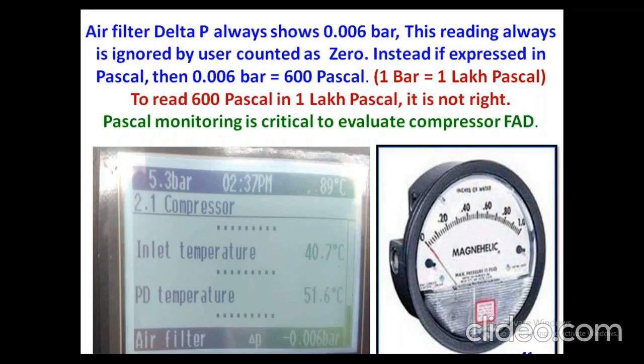Either this console has to be remodified and the resolution improved, or you have to add an add-on, a digitized one with an alarm. When there is a full flow, automatically it gives an alarm, then it needs to be cleaned. The air intake pre-filters have to be cleaned.